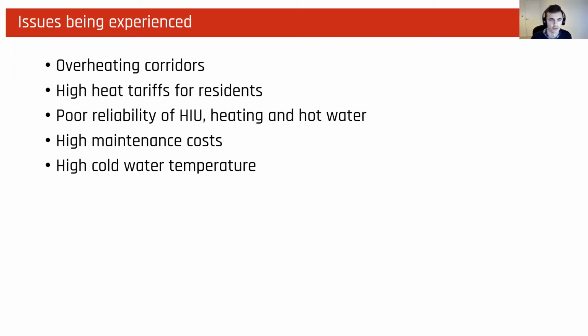And what came out of that really was that we had issues on the site which consisted of overheating of corridors. So it's commonly found that there were high ambient temperatures in corridors, which is a resident comfort issue. Also, the required heat tariff on site was causing a very high cost of heat. Also, the reliability of the HIU wasn't where it needed to be. So we're actually seeing a lot of valves failing on sites at the HIU, which is causing issues with heating and hot water supply. So that was a clear resident comfort issue there.